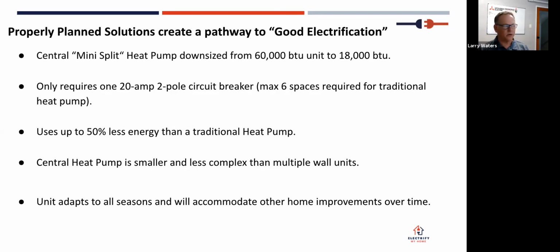This particular system we installed in her house only required one circuit breaker—two poles, two switches, 20 amps, running that entire system off 20 amps. It uses 50% less energy than a typical heat pump and is smaller and less complex than wall units. A lot of typical HVAC contractors, when you talk about mini splits, want to put a unit on each wall in the house. This is way less complicated, works way better, and is less costly, and it adapts to all seasons. These units speed up and slow down, so we can size them for whatever season. As you improve your house with new windows or insulation, these systems automatically adjust their capacity to be the right size for your house, no matter the conditions.